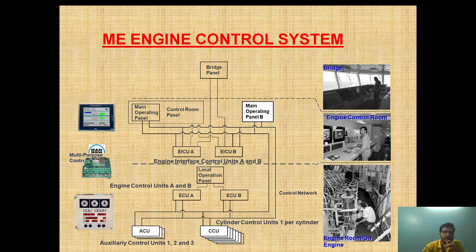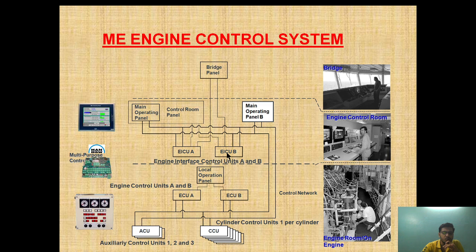As you can see, this is the flowchart diagram of the main engine control system. Suppose a signal of dead slow ahead is given from the bridge — what will happen after that? It will come down to the engine control room, where it will go to main operating panel A or main operating panel B, and after that it will go to EICU A or EICU B. Only one of them will be functioning and the other will be on standby. From EICU it will go to ECU A or ECU B, and from ECU it will go to the individual cylinder unit.